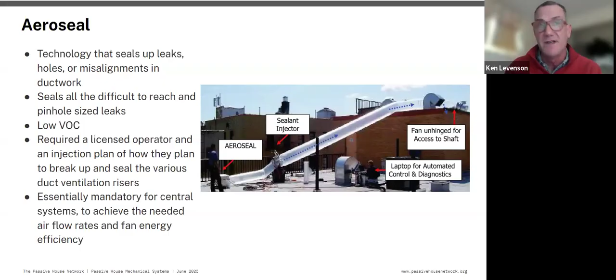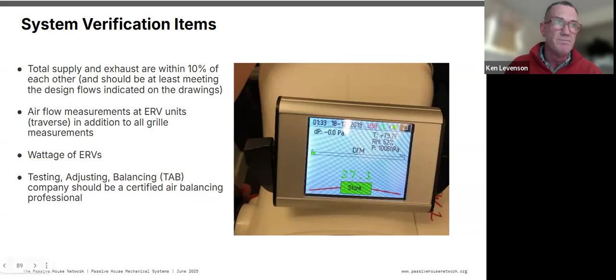You're testing the big systems too, which may have monitors saying 'oh it's doing this, it's doing that.' Passivhaus requires physical measurement at the exhaust and the intake to the exterior, to know that we're within 10% of each other.